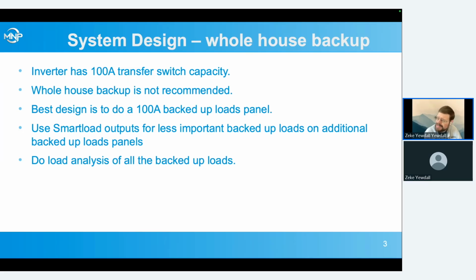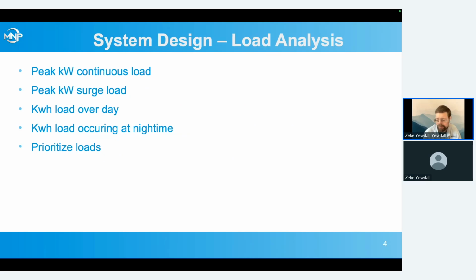One thing that seems to be missing on a lot of installations nowadays is doing a load analysis of the backed up loads. 30 years ago, whenever we were designing an off-grid system, we would always calculate our peak continuous load, our peak surge load, how many kilowatt hours load we expected over the day, how much percentage of that was at nighttime operating off the batteries, how much might occur during the daytime, and prioritizing the loads. Like, can we put more of our heavy loads in the daytime, in the afternoon when our batteries are full and we have extra solar, versus running them at nighttime when we're pulling our batteries down more.